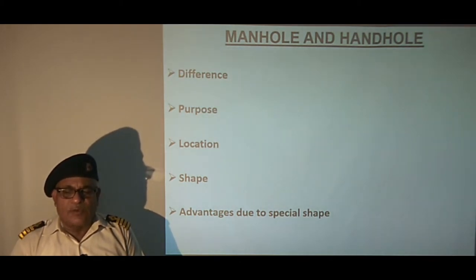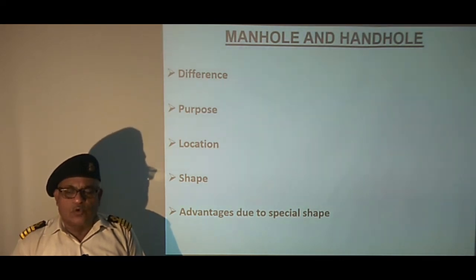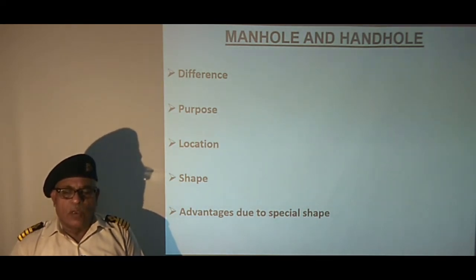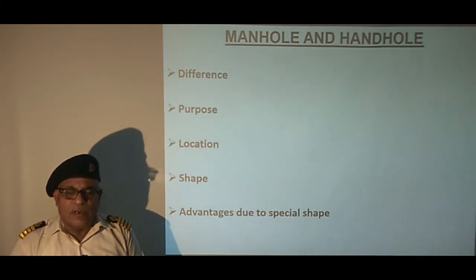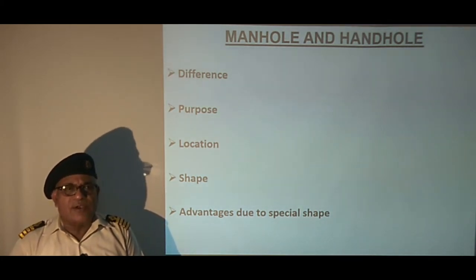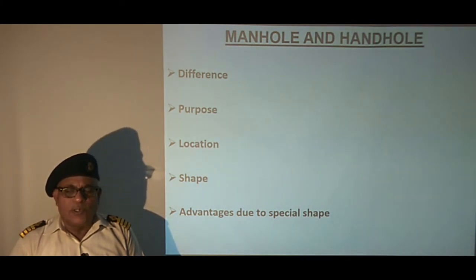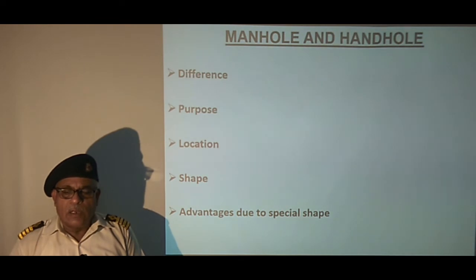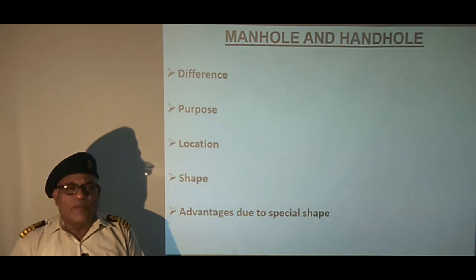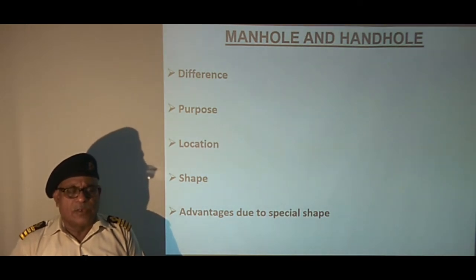Elliptical cover is fitted to the boiler from inside where steam assists to close it. Studs are not subjected to steam pressure, thus they can be made lighter. For the same reason, dogs need not be highly stressed and nut can be tightened just to prevent steam leakage.